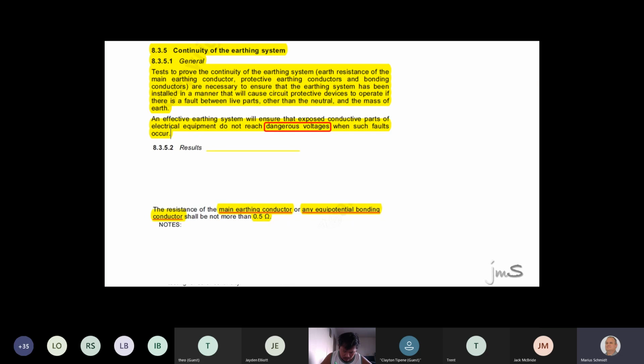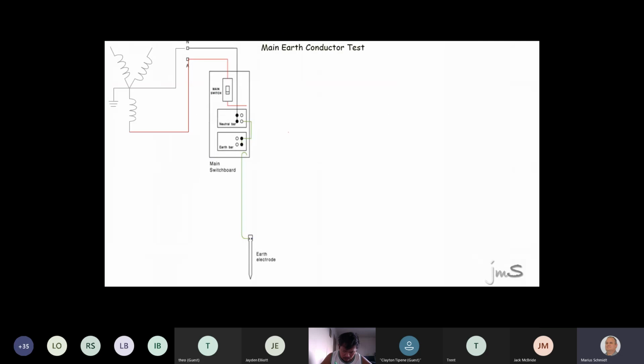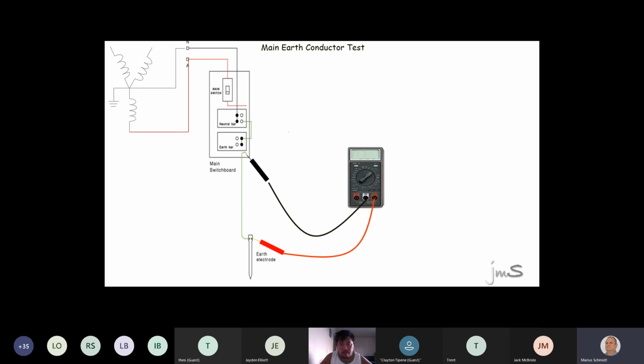Right, I'm going to take this now and I'm going to ask you questions. Firstly, you take your main earth wire and you connect your multimeter between the beginning and the end. Are you guys happy with that? And what type of instrument will I use to measure ohms? Is it an ohm meter, a voltmeter, or an amp meter? Right, they ask you that. Now, where do you put the wires? Obviously, the leads you're going to put at the beginning and end of that wire. You're going to press test.